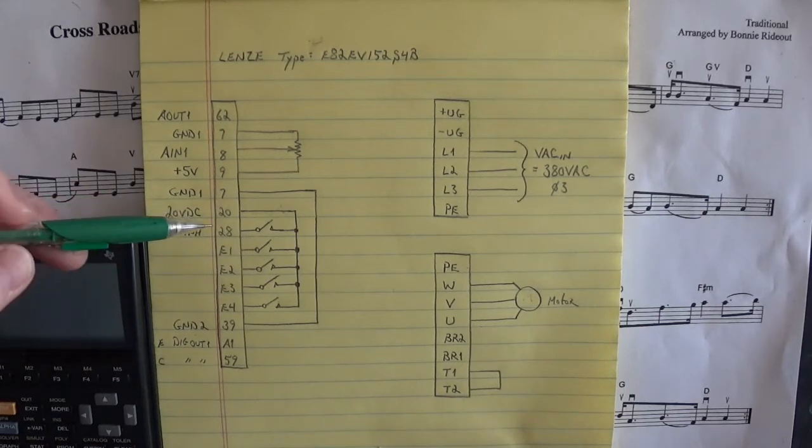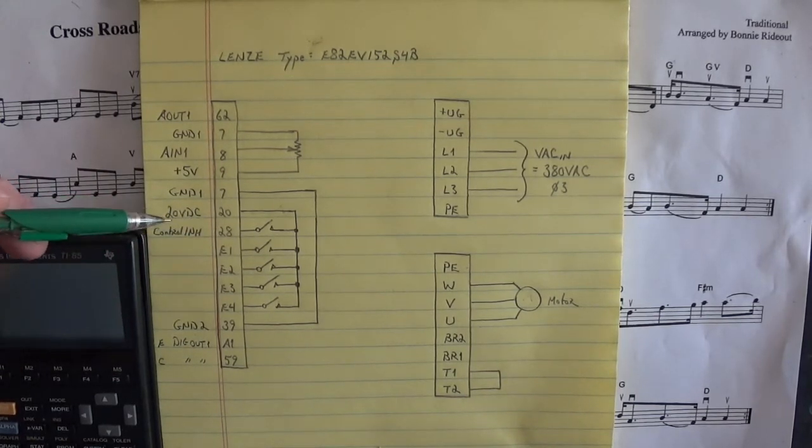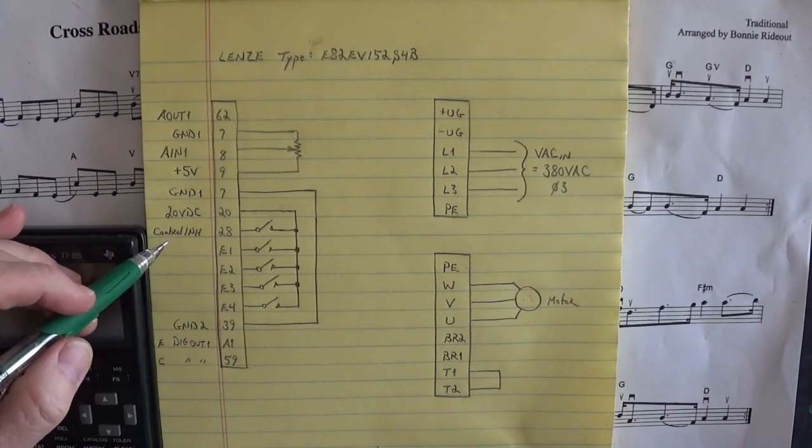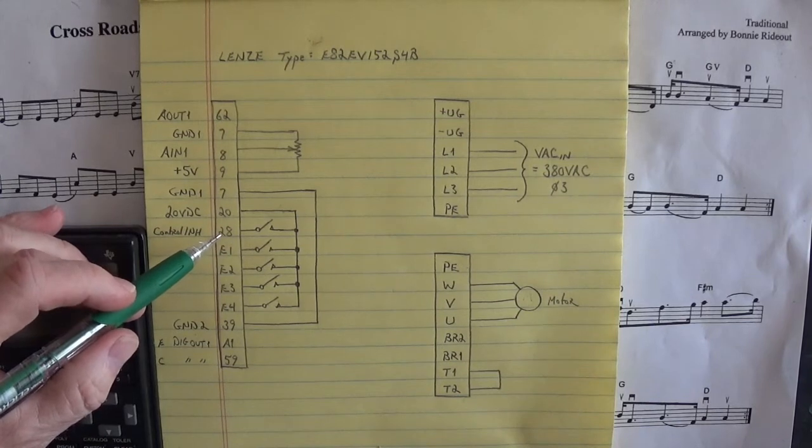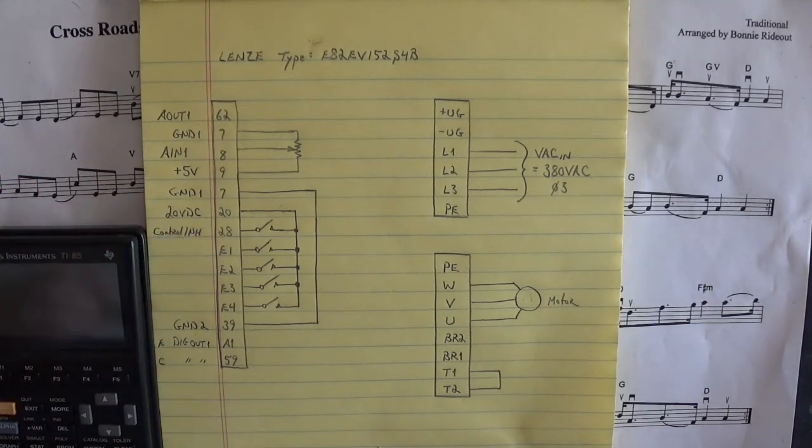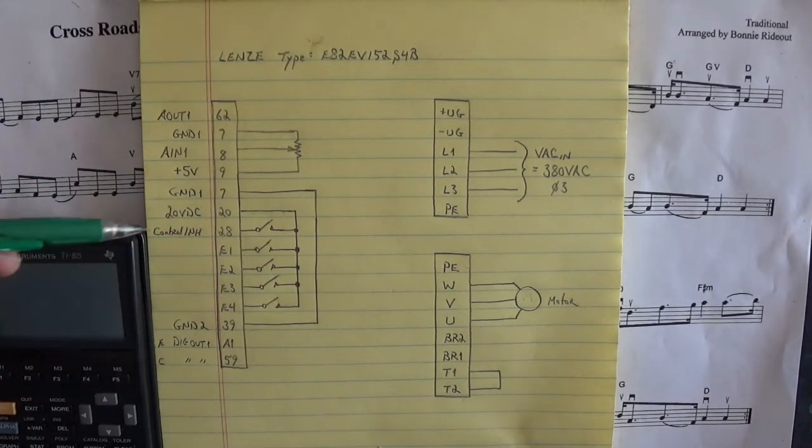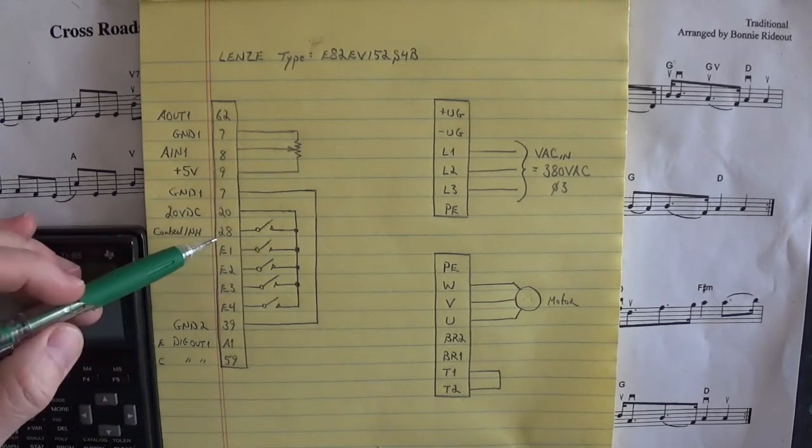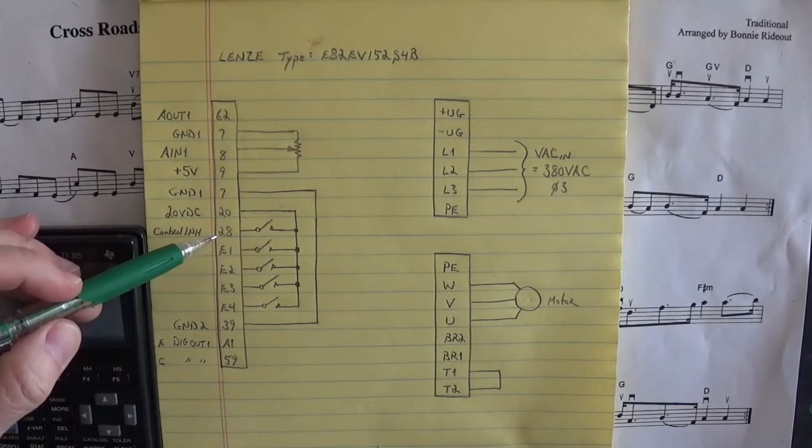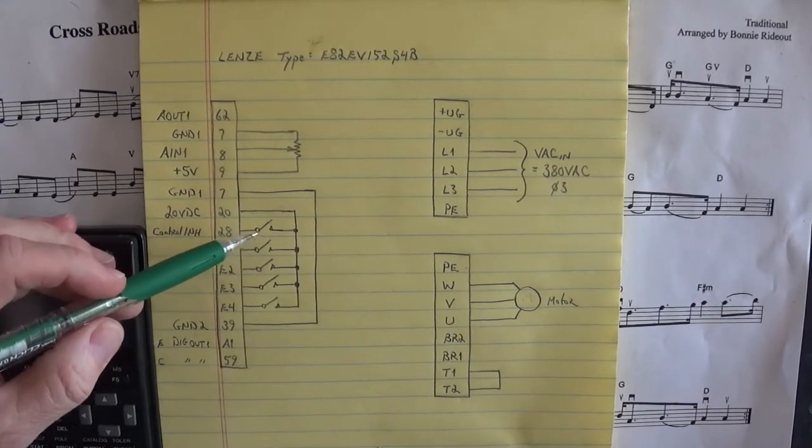Here are the inputs. There's one input that has to be made - that's the control inhibit input. That pulls the drive out of inhibit when you tie pin 20 to pin 28 through this switch right here.